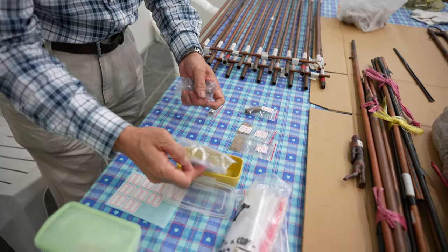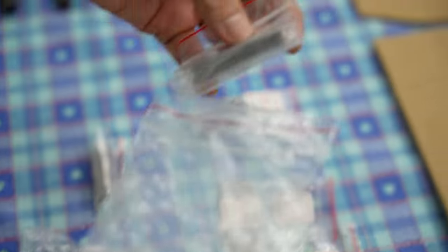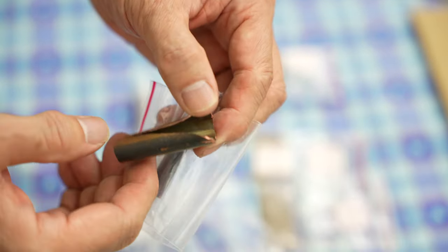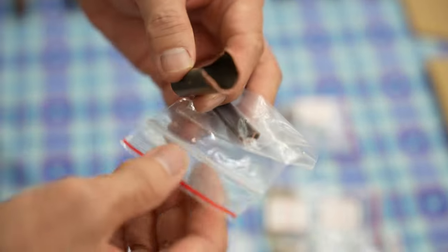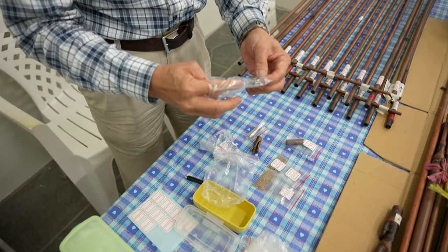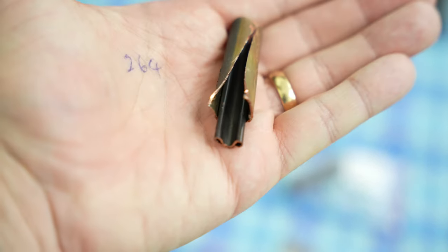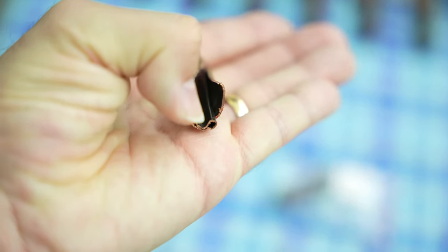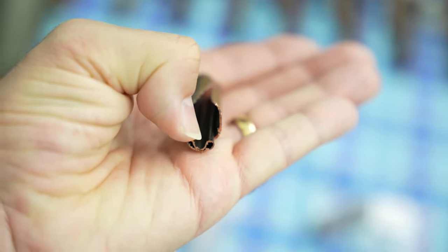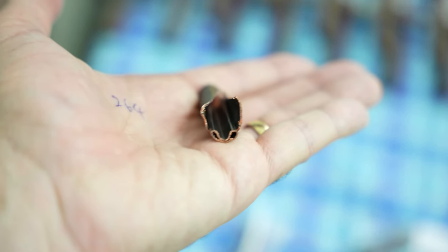So this is the damage very clearly. It's just literally torn it open. Not only pressed the inner pipe in — when it ran out of the ability to deform the inner pipe, we can see the internal deformation. So we're just looking at the internal deformation.